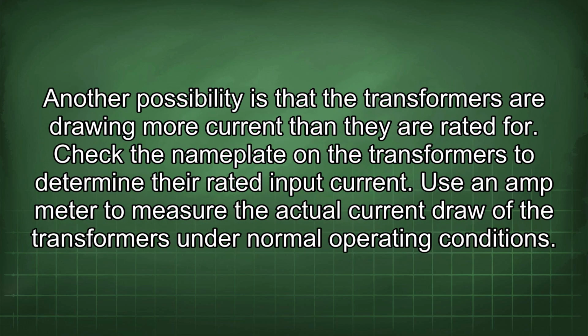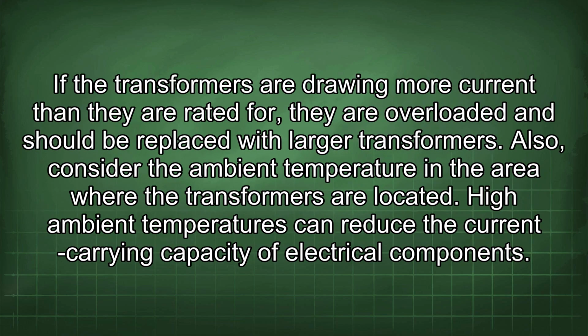Another possibility is that the transformers are drawing more current than they are rated for. Check the nameplate on the transformers to determine their rated input current. Use an amp meter to measure the actual current draw of the transformers under normal operating conditions. If the transformers are drawing more current than they are rated for, they are overloaded and should be replaced with larger transformers.